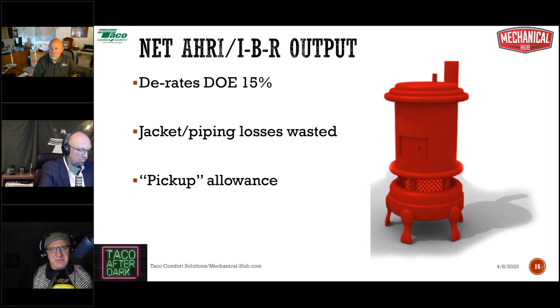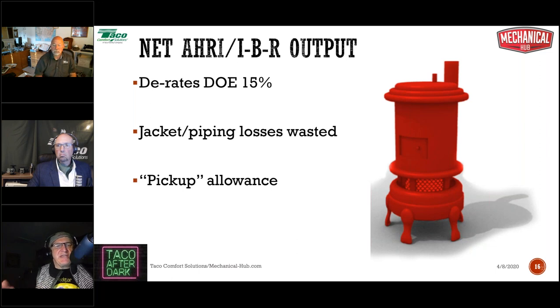Another part of the 15% was for something called the pickup allowance. And IBR defined the pickup allowance as the amount of energy needed to heat up the delivery system. We're talking about old systems with cast iron radiators, cast iron baseboard, and black iron pipe, all right? You needed to heat that pipe up before you could deliver heat through it to a room. So the pickup allowance is a certain amount of energy set aside to heat up the delivery system, all right?